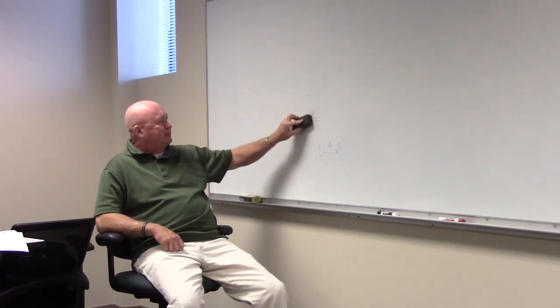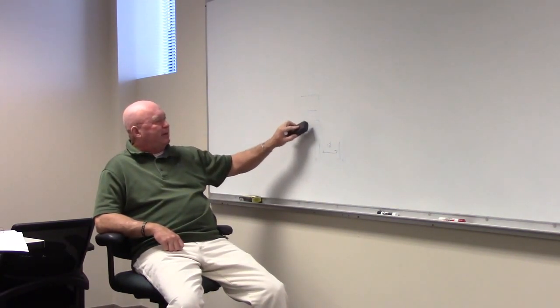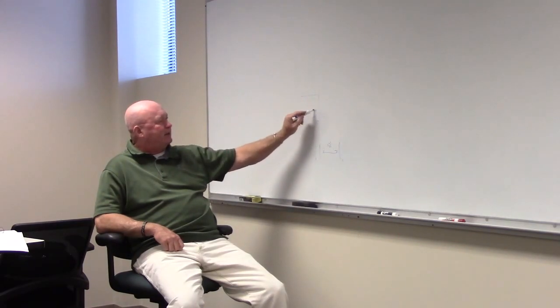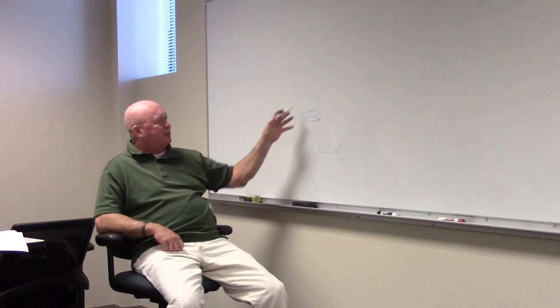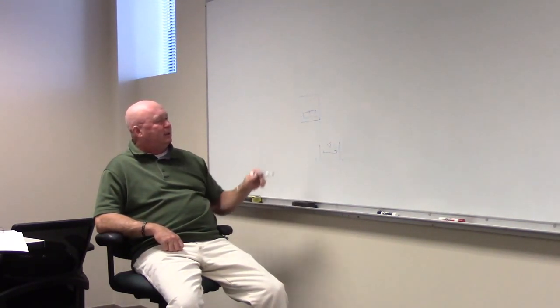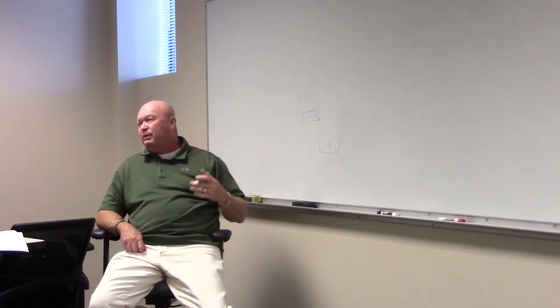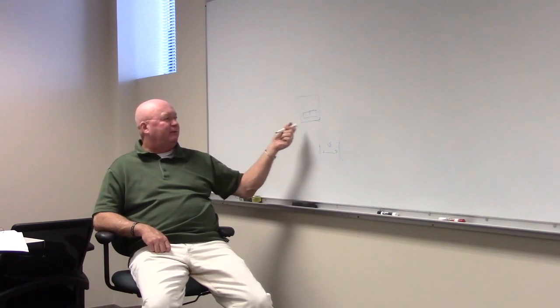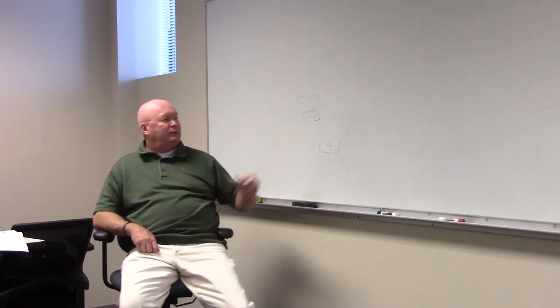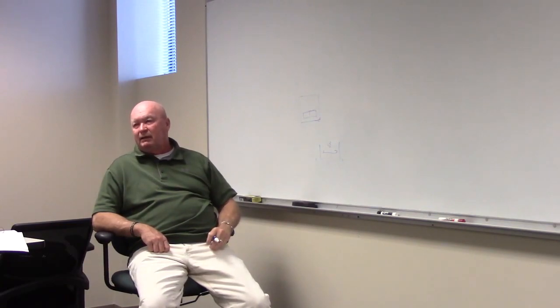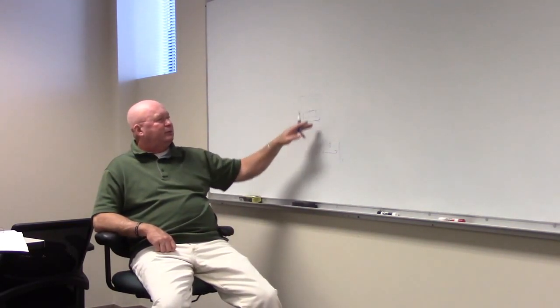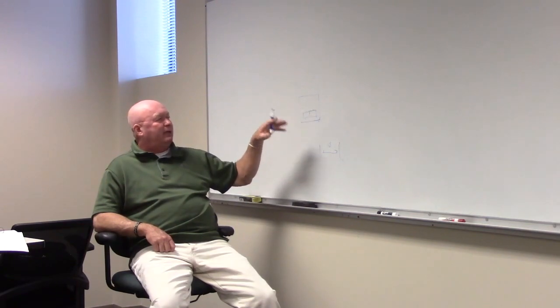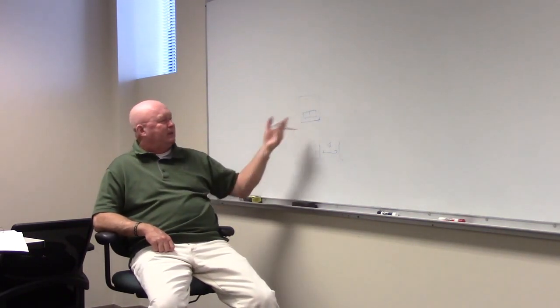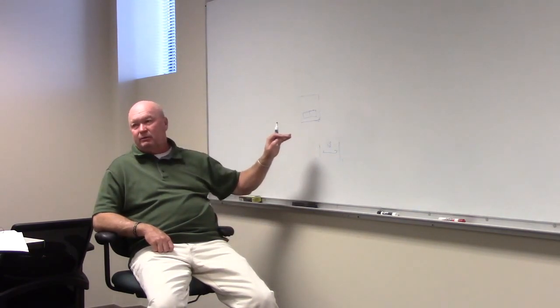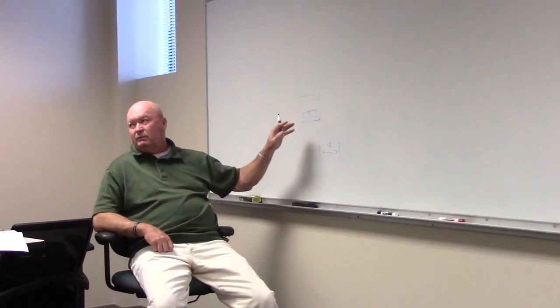So the biggest thing is understanding, and usually from the project manager, if you're in the field, you're getting a layout. In fact, I usually give them a printed copy from Duke Energy, because it usually gives you the requirements for the pad and the size, and whether it's got to be a small pit or a flat pad. There are 2 types of pad: a flat pad and a pit pad. Most of the time, the larger services require a large pit pad. Those are just recommendations from Duke Energy, and we usually get the general contractor to build the pad. We don't want to, because we're not concrete people, right? We don't want to build pads.